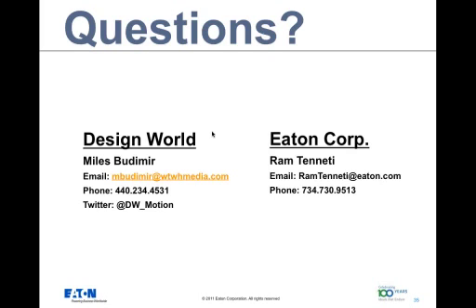All right. Here's another question from James. He wants to know, do soft starters require any special fusing or protection? Again, there has to be a line interruption mechanism ahead of the soft starter, whether it's a breaker or a fuse, and that is purely dictated by what kind of safety mechanism you want to have in the loop. It's no different than what you're already using today for your across the line or any other reduced voltage mechanism. There's nothing specific that is required for a soft starter. Okay. All right.